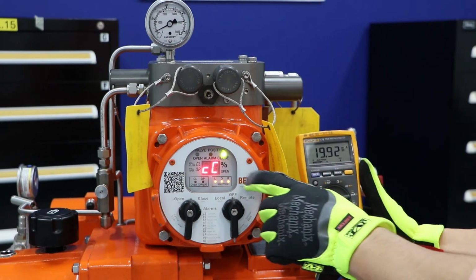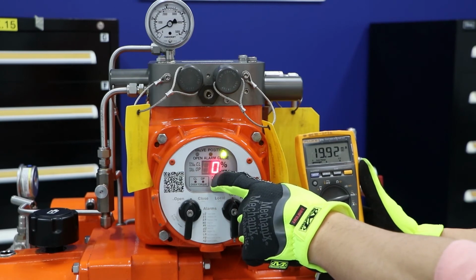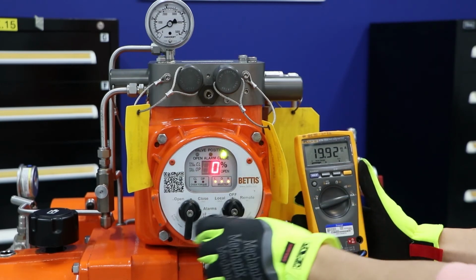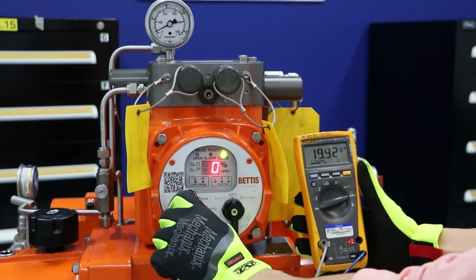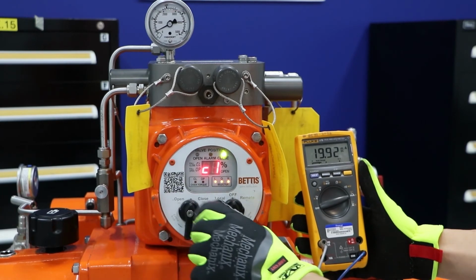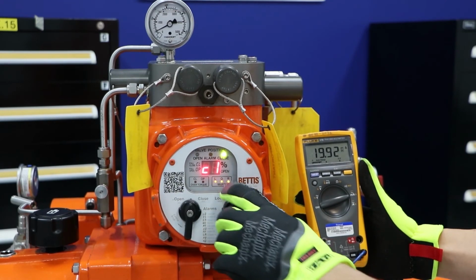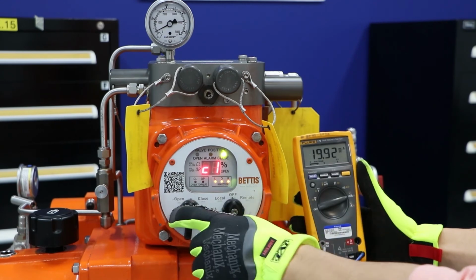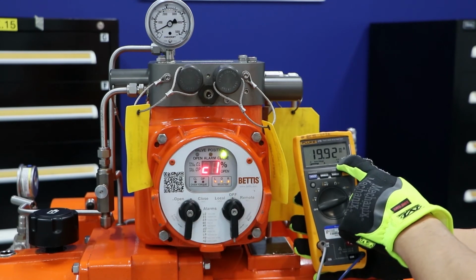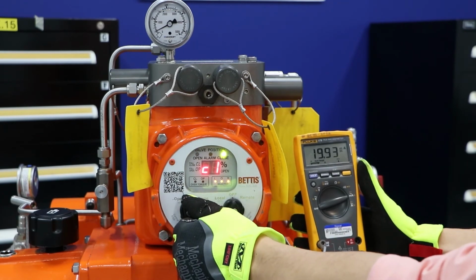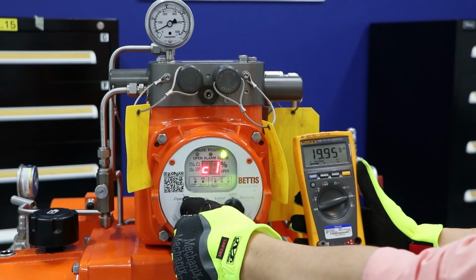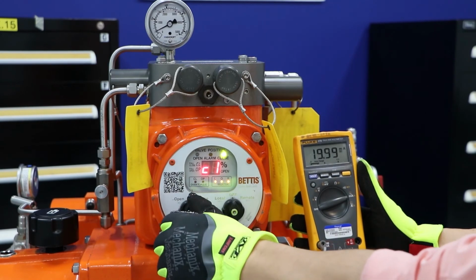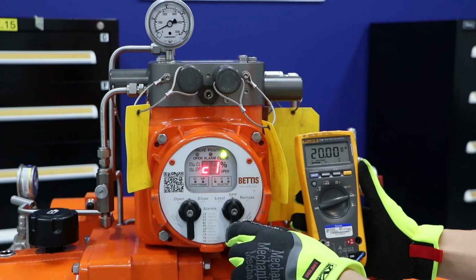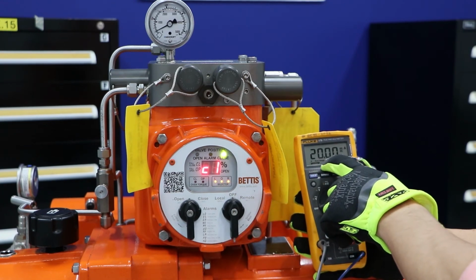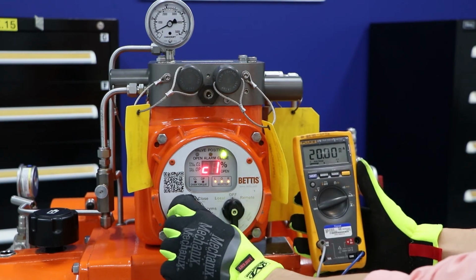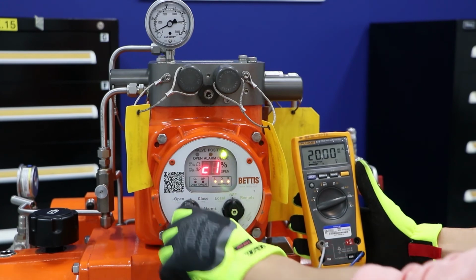So we need to increase this value. In order to increase it, our calibration choice, or CC, should read 0. In this case, it's reading 0. So we'll go ahead and hit yes. Okay. Now it reads C1. And what we want to do here is we want to hit no until this number reads 20 milliamps. Great. Now our multimeter reads 20 milliamps. Now we accept that value and we say yes.